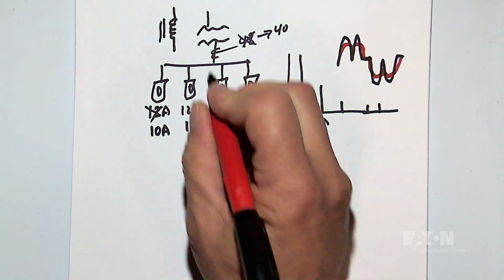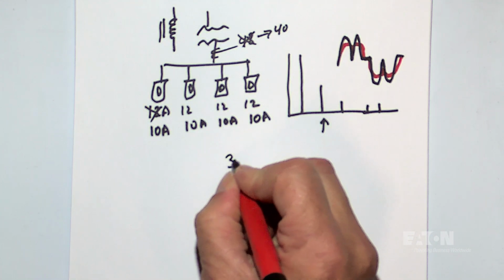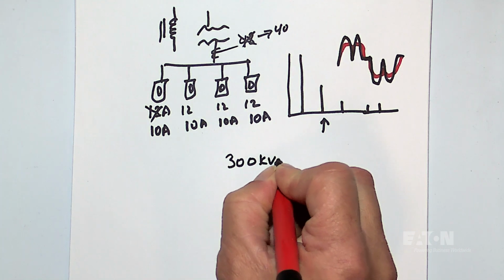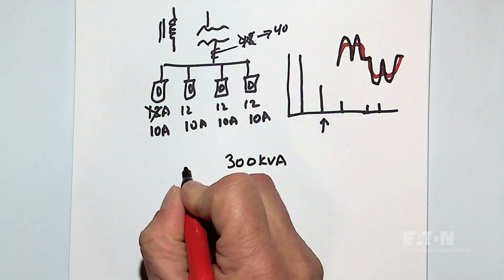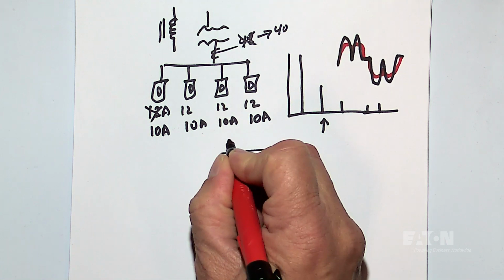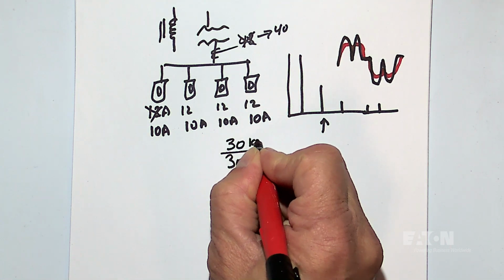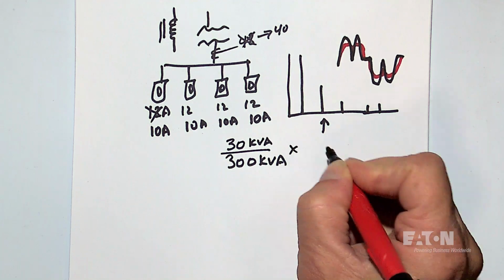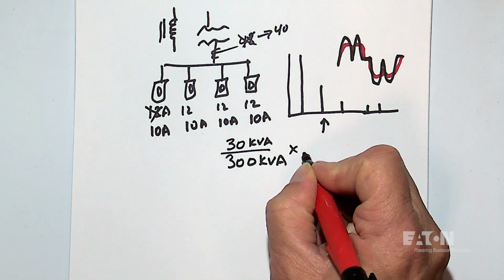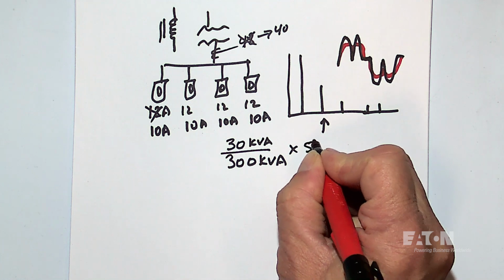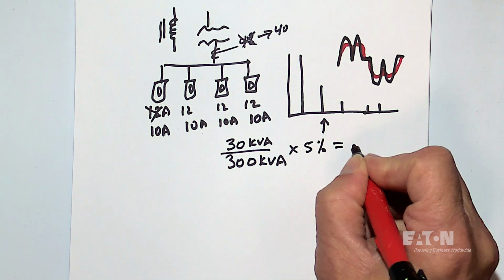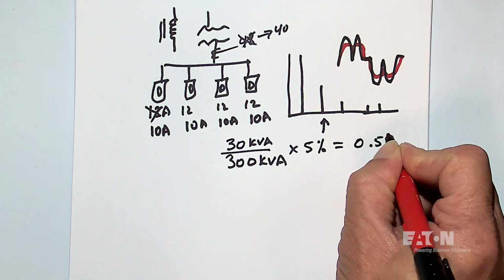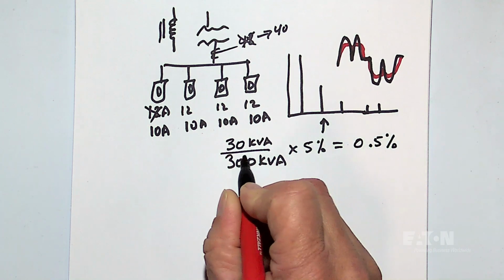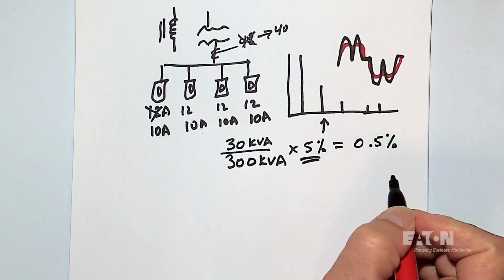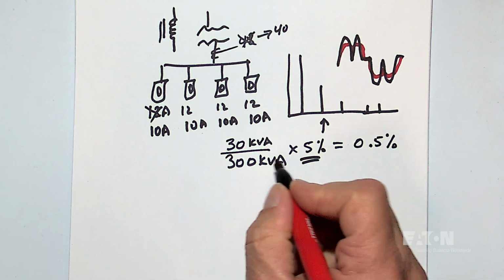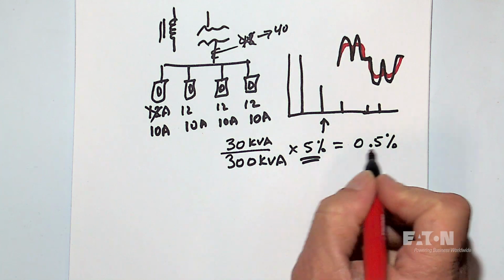Now, why is that the case? Let's say that transformer is 300 kVA, okay? And let's say that each drive is 30 kVA. So to get the actual impedance, we would take 30 kVA or 30 horsepower divided by 300 kVA for the transformer times the impedance of the transformer. Let's say it's 5%. That turns out to be 0.5%. And so the effective impedance of that transformer at a very light load with one transformer is 0.5%.